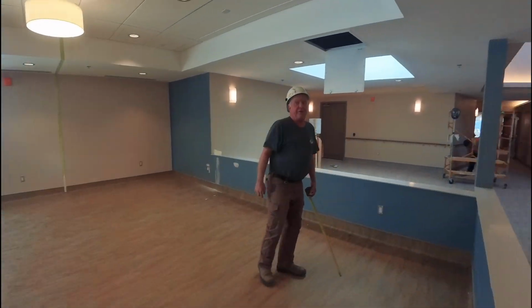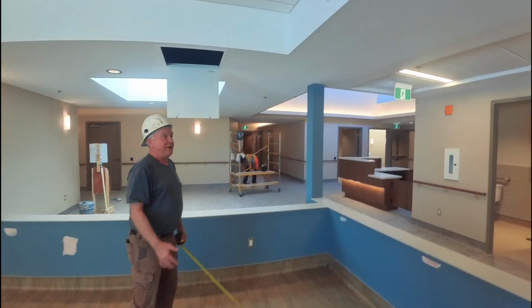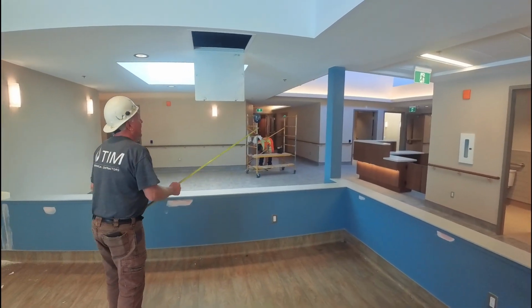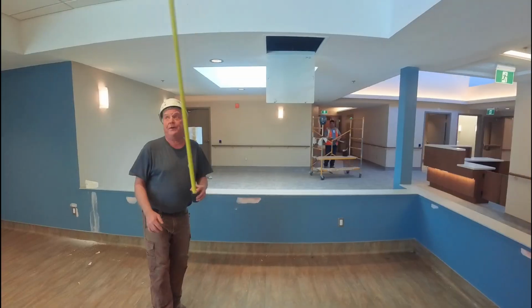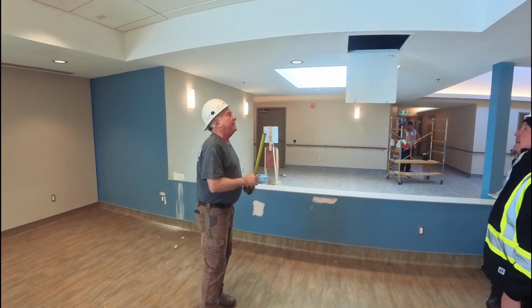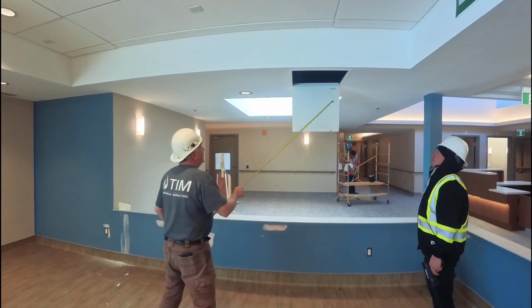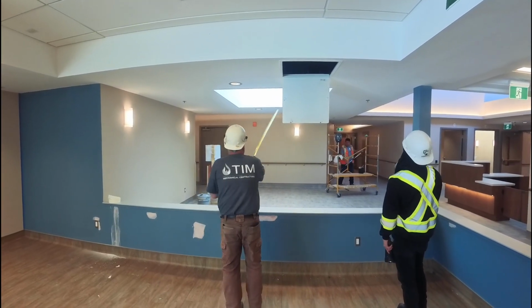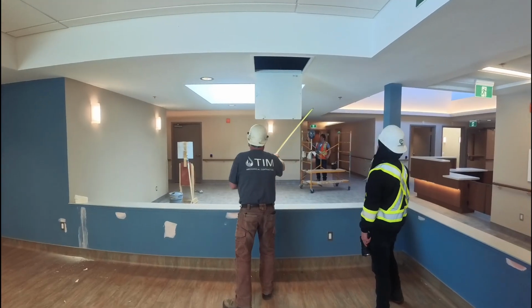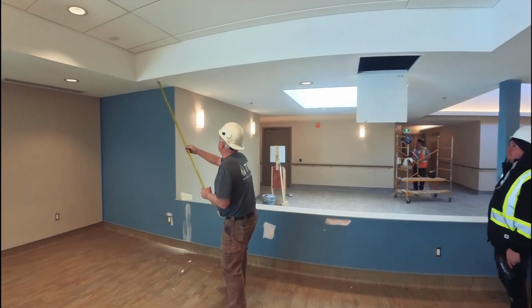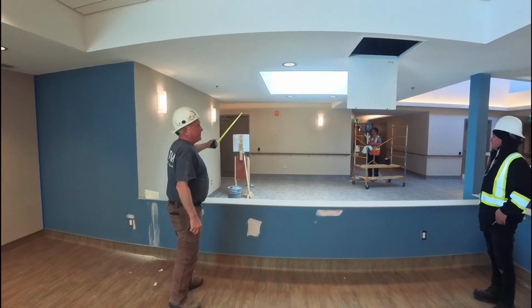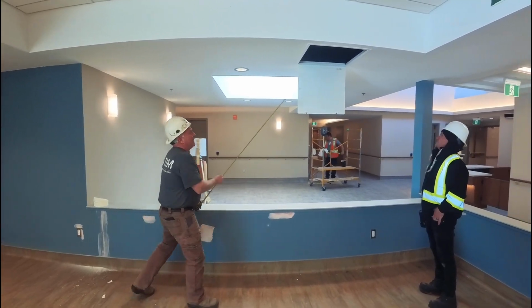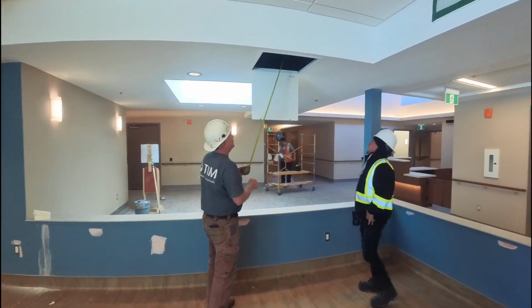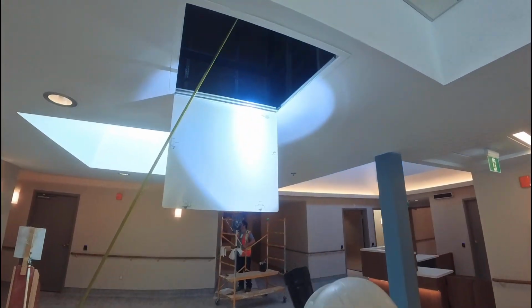The other large unit that takes care of each wing is a makeup air unit. It's sitting directly above our heads here on this side of this large common area. It has a supply and a return as well. The supply duct runs on this side of this skylight opening. The return drop comes down through here and runs down through this side of the skylight. So the main balancing damper for the supply is through this access door up here. You can look up there, Jay, and you'll be able to see that, always on the supply side, the duct is thermally wrapped with insulation on the outside.